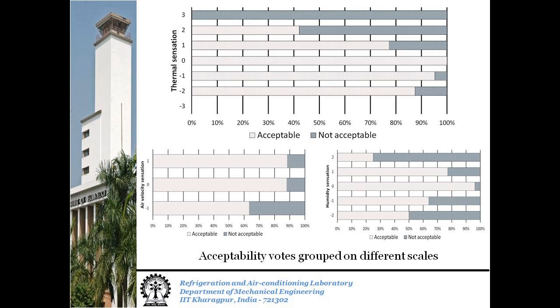When humidity is not felt to be just right, acceptability is greatly compromised. But over the survey, we found that 82% of the votes were for humidity being just right or slightly humid. This was even though partial pressure of water vapor at 3 kPa was recorded on three separate days. This speaks to a remarkable level of acclimatization to humidity amongst the occupants.